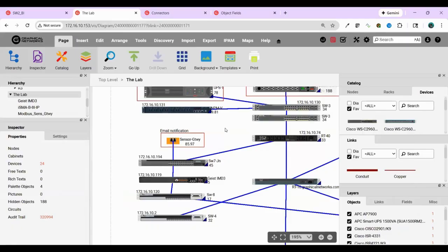How can you find out what those OIDs are? Well, usually you can request the information from the manufacturer. You can grab it via an SNMP walk. A lot of times you can certainly use an AI tool to do a lookup of, hey, how do I get temperature out of this particular device type and manufacturer? And you'll typically get results. Obviously, if they're manufacturers you purchase from and you have support agreements, you can usually request that they let you know what the OIDs are that you can monitor for specific items.